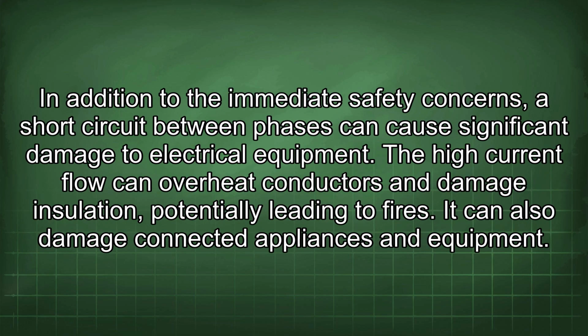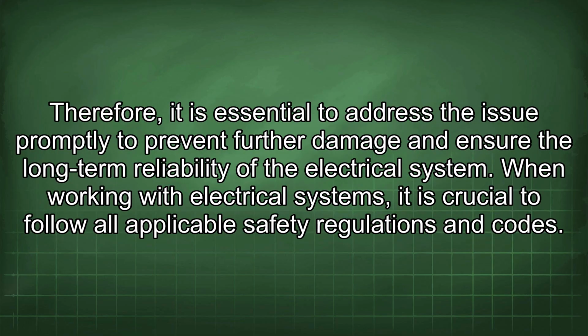In addition to the immediate safety concerns, a short circuit between phases can cause significant damage to electrical equipment. The high current flow can overheat conductors and damage insulation, potentially leading to fires. It can also damage connected appliances and equipment. Therefore, it is essential to address the issue promptly to prevent further damage and ensure the long-term reliability of the electrical system.